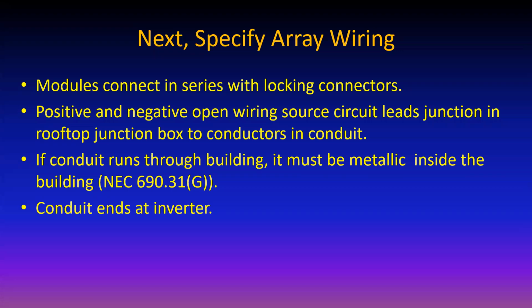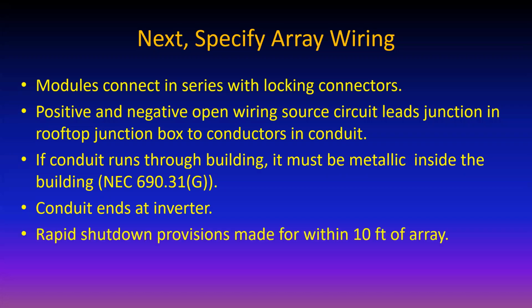Conduit ends at the inverter or maybe at the AC, or there may be a DC disconnect ahead of the inverter, but usually not. And the rapid shutdown provisions need to be made within 10 feet of the array according to the 2014 code, but they need to be made a lot closer according to the 2020 code. But there's a lot of equipment out there to be able to meet this requirement at this point, and so nobody's having any problems with this.